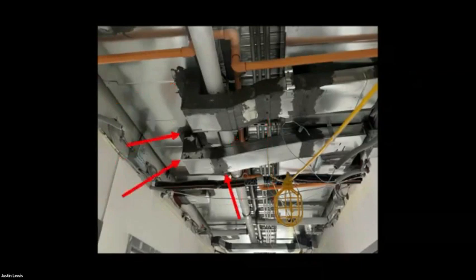That one jogs over before it gets into the room. So when we think about all of these, the 100-plus taps like this running through 3 stories of the building, we can really see how added static pressure that's not accounted for can really start impacting the overall system.